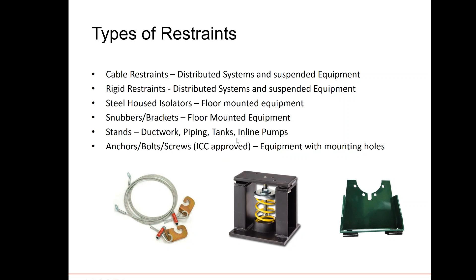So I'll just leave you with one thing with regards to the equipment and the product that you use. It must be included in the submittals and stamped by a professional engineer. For example, you can't just select something, put it on and say, okay, I put a snubber around this air handling unit. The design must be calculated so that an engineer of record can determine that the seismic restraint that is being used is sufficient to withstand the forces. Since the forces vary by location to location, floor to floor, equipment to equipment, a calculation needs to be done to ensure that the restraint can overcome those forces.